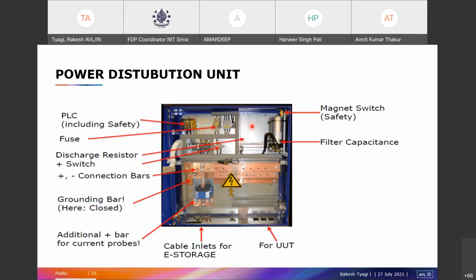Discharge resistor means, when I switch on the panel and use it for DC supply, and then switch off, say I'm working from 9 to 6 o'clock and switch off at 6 in the evening, the charge DC voltage is still there. It takes around 15 to 20 minutes for whatever charge was there to get discharged.